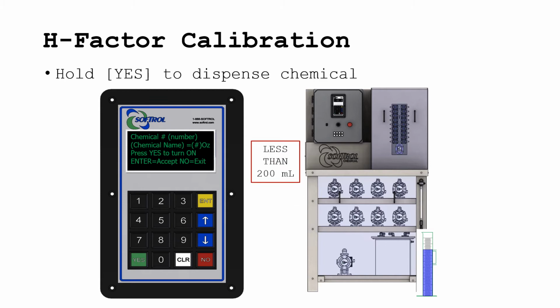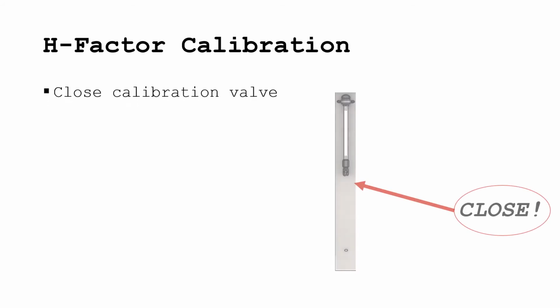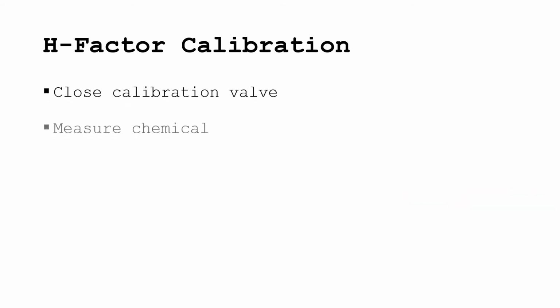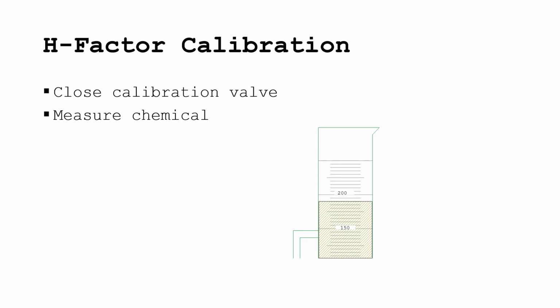Remember, the injection size does not have to be a perfect match. After the injection, close the calibration port valve on the front of the system, and then measure the chemical, remembering to convert milliliters to ounces and to avoid measuring the foam.